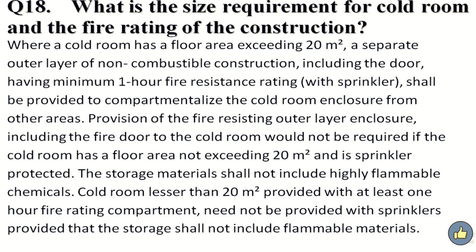Answer. Where a cold room has a floor area exceeding 20 square meters, a separate outer layer of non-combustible construction including the door having minimum 1 hour fire resistance rating with sprinkler shall be provided to compartmentalize the cold room enclosure from other areas. Provision of the fire resisting outer layer enclosure, including the fire door to the cold room, would not be required if the cold room has a floor area not exceeding 20 square meter and is sprinkler protected. The storage material should not include highly flammable chemicals.